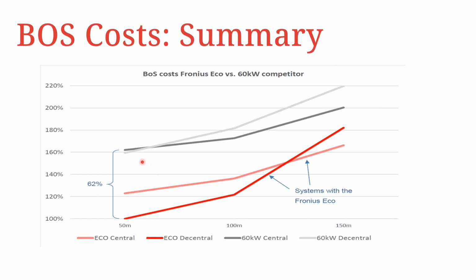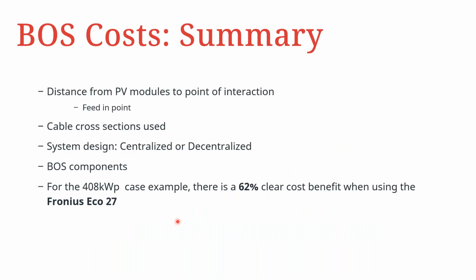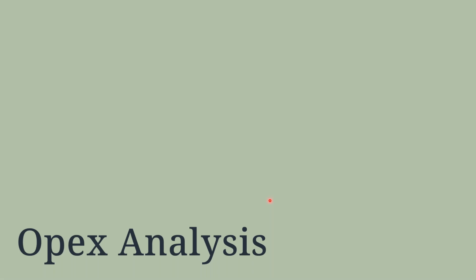So let's look at the summary, as you can see from this table. In summary, there is a whopping 62% between the highest variation of the 60 kilowatt competitor and the lowest variation of the Fronius Eco 27. This means it is much more profitable to employ the Fronius option for both centralized and decentralized system design. So for the 408 kilowatt peak case example, there is a clear 62% cost benefit when using the Fronius Eco 27. Good. That was the CapEx analysis.